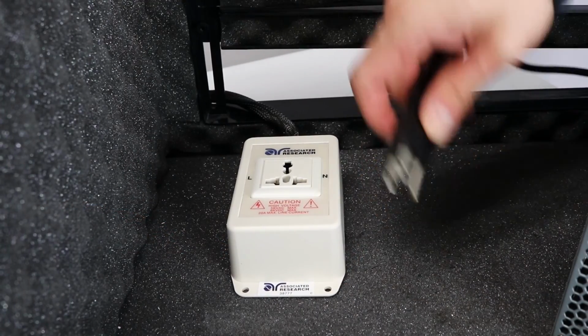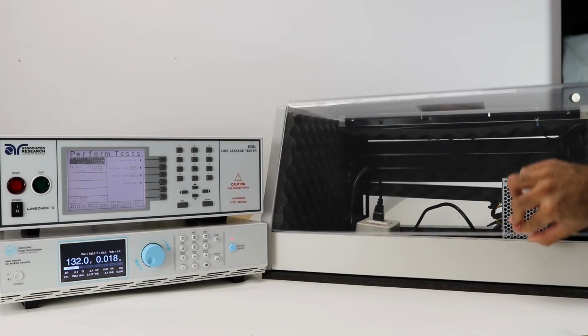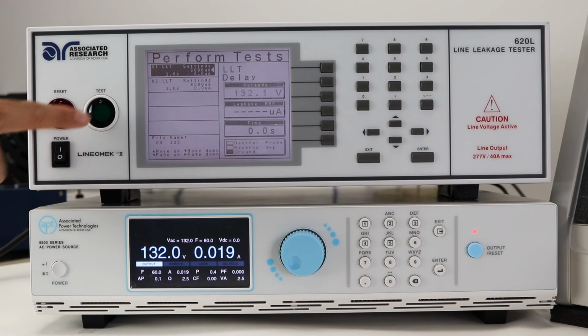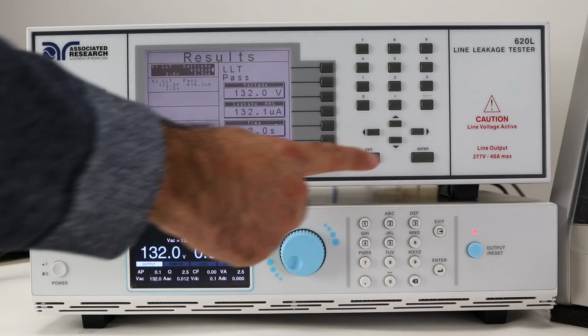To connect the DUT to the linechek, simply plug in the Class 1 DUT into the adapter box. Close the DUT enclosure door and stand back. Push the test button to run your test sequence. Once your test sequence has completed, use the arrow keys to review your results.